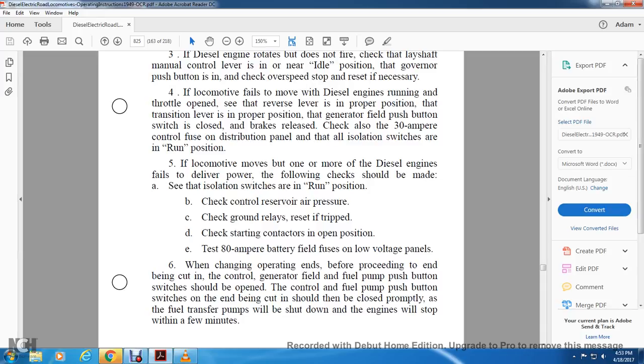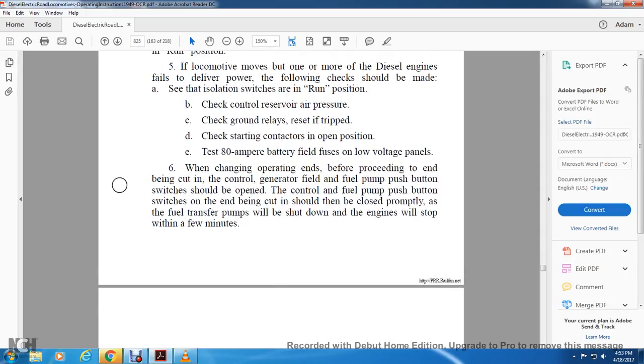When changing the operating ends, before proceeding to the end being cut in, the control generator field and fuel push button switches should be open. The control fuel pump push button switches at the end being cut in should then be closed promptly. If the fuel transfer pumps shut down, the engines will stop within a few minutes.